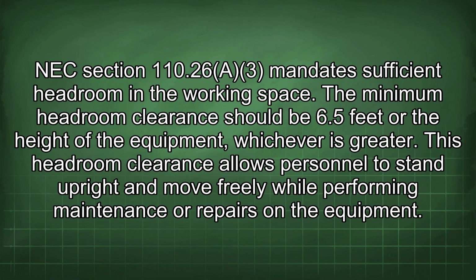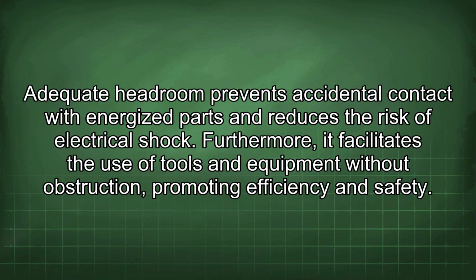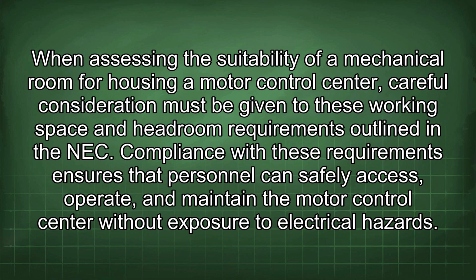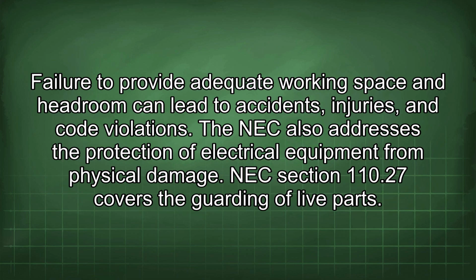This headroom clearance allows personnel to stand upright and move freely while performing maintenance or repairs on the equipment. Adequate headroom prevents accidental contact with energized parts and reduces the risk of electrical shock. Furthermore, it facilitates the use of tools and equipment without obstruction, promoting efficiency and safety. When assessing the suitability of a mechanical room for housing a motor control center, careful consideration must be given to these working space and headroom requirements outlined in the NEC. Compliance with these requirements ensures that personnel can safely access, operate, and maintain the motor control center without exposure to electrical hazards. Failure to provide adequate working space and headroom can lead to accidents, injuries, and code violations.